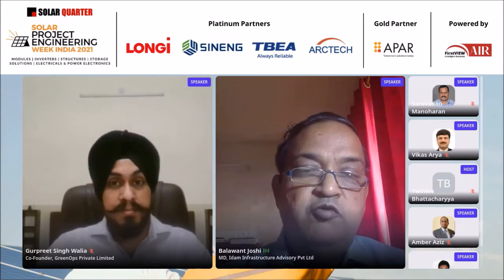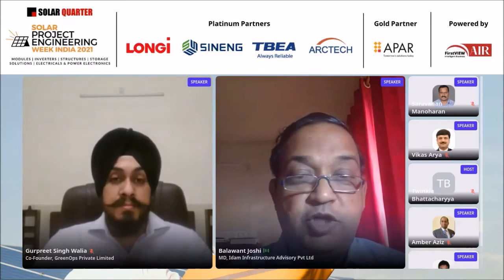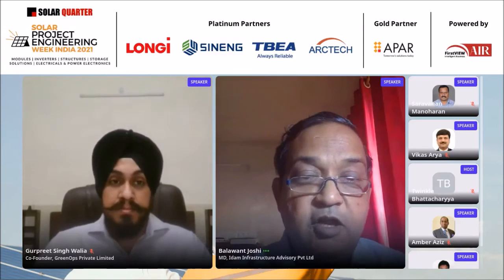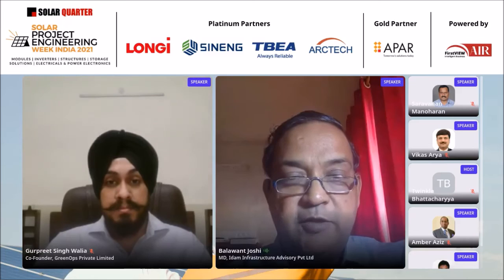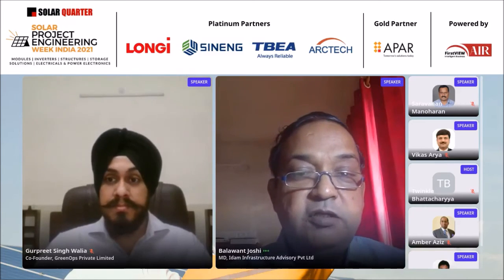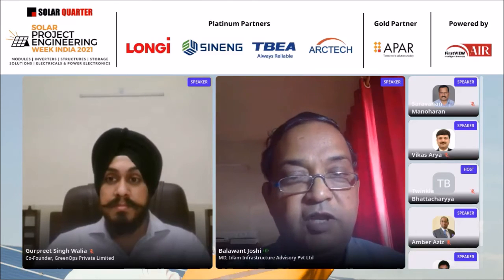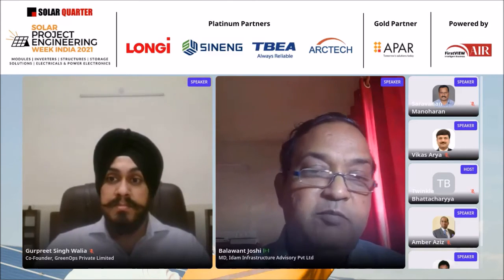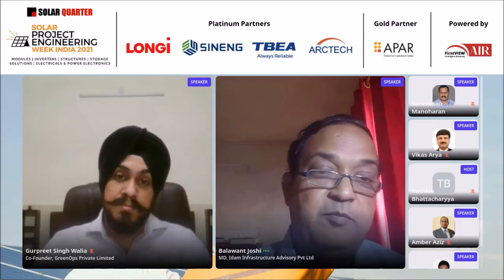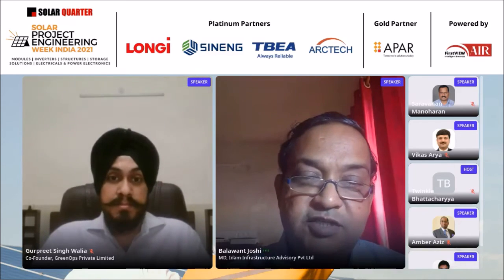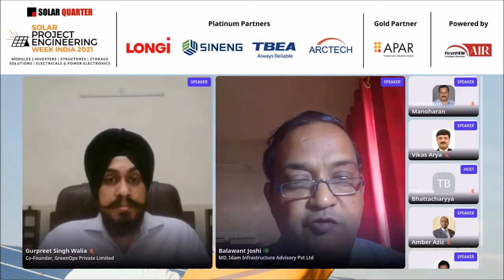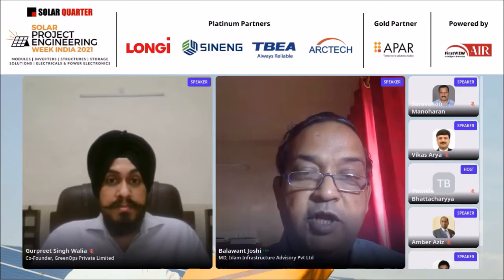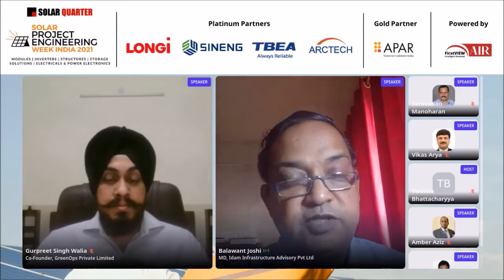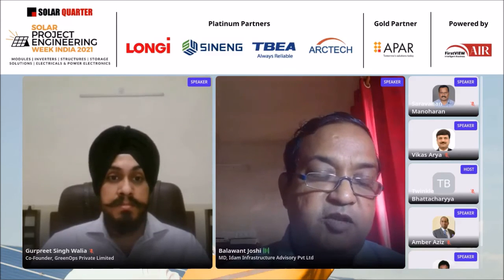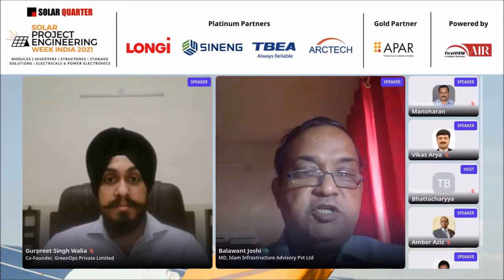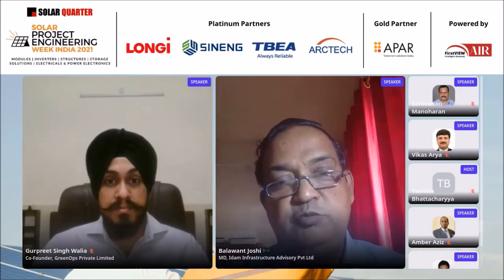Right now, a battery storage that is megawatt-hour scale, not kilowatt-hour scale at a C&I end, and not the huge battery storage required at a generator end, but battery storage viable at a 33 kV, 11 kV level, utility scale, 4 megawatt-hour or 10 megawatt-hour, can be used for capex deferral, ancillary services benefit, ramp rate benefit, and energy shifting. All the benefits can be given when you put it as a co-located, distributed solar plus battery storage system. That's what our analysis on several assignments shows, done for large scale projects, small scale projects, as well as mid-size distribution company related projects.